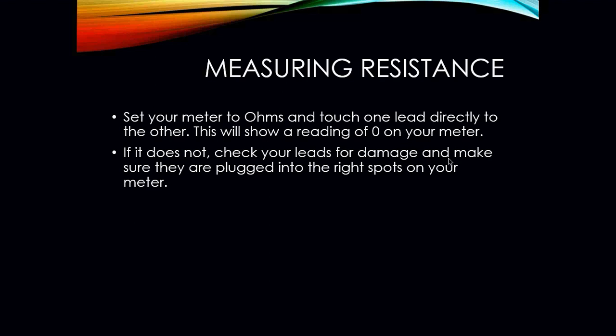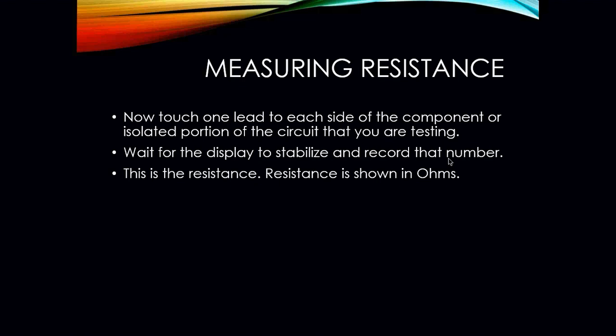Touch one lead directly to the other, and this will show a reading of 0 on your meter. Always test your meter when you're taking a resistance reading. You want to see 0 on your screen, because that's telling you that the meter is still good. If it does not, check your leads for damage and make sure they are plugged into the right spot on your meter. Okay, touch one lead to each side of the component or isolated portion of the circuit that you are testing. Again, wait for that display to stabilize and then record that number. And then again, that is your resistance reading. Resistance is measured in ohms.